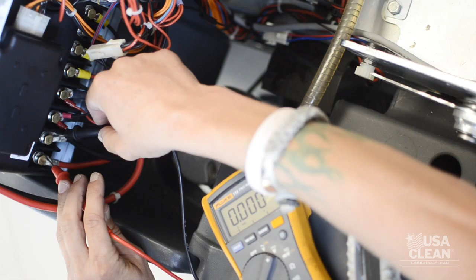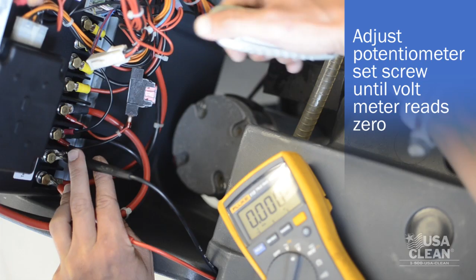If it does not read 0, here's how you adjust your potentiometer. With your leads still on the control board, take your Allen head and insert it into the set screw on the potentiometer. Turn the set screw until your voltmeter reads 0. Once it reads 0, you have successfully set your potentiometer.